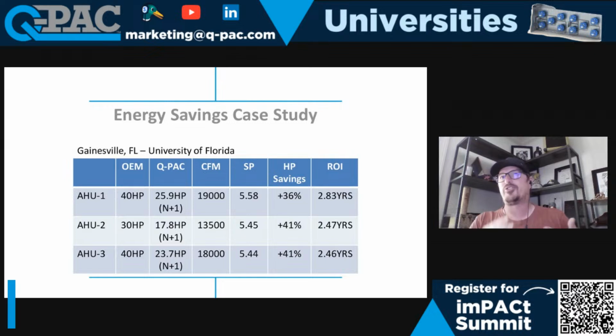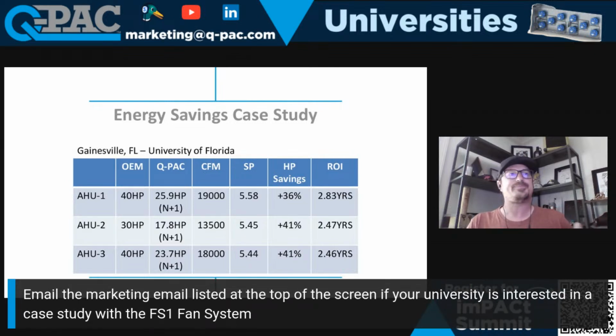All the slip losses and electrical losses that they may find, it would be difficult to give a precise idea. But if I can give an AC number at full load and an EC number, we're still basically telling you that you're going to get about a 3 year payback based off those numbers. If we're running anything at partial loads or on a VFD where you've got added losses, those numbers could be a lot faster on your payback side.